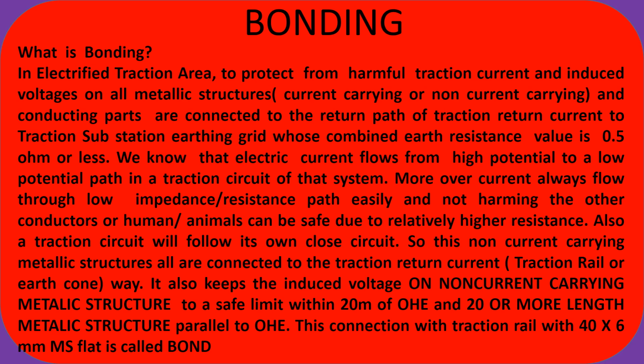And conducting parts are connected to the return path. That means one leg of the traction, or the return path of traction return current, goes to the traction substation earthing grid, whose combined earth resistance value is 0.5 ohm or less.